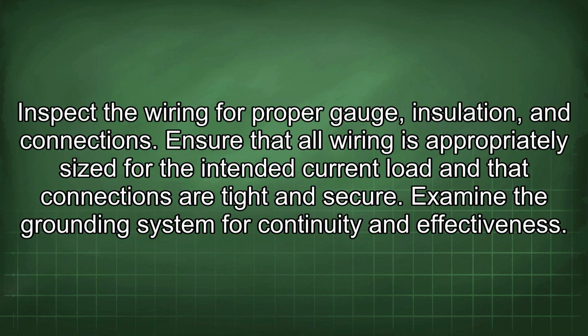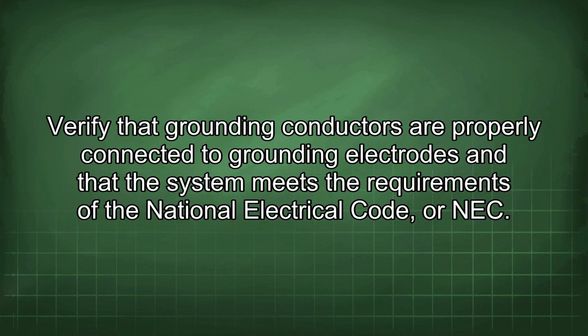Inspect the wiring for proper gauge, insulation, and connections. Ensure that all wiring is appropriately sized for the intended current load and that connections are tight and secure. Examine the grounding system for continuity and effectiveness. Verify that grounding conductors are properly connected to grounding electrodes and that the system meets the requirements of the National Electrical Code, or NEC.